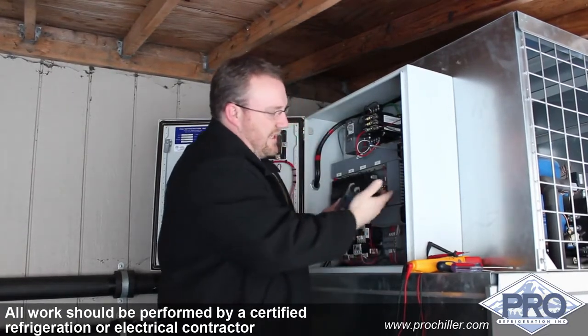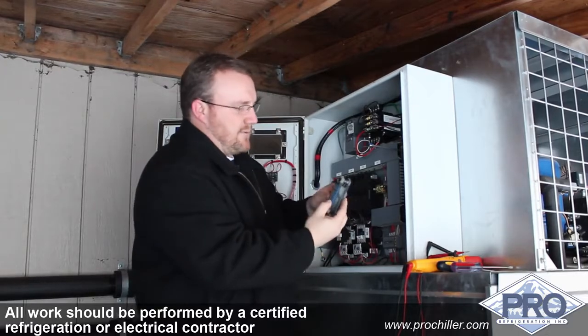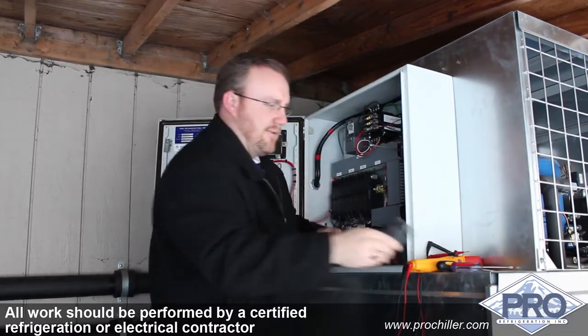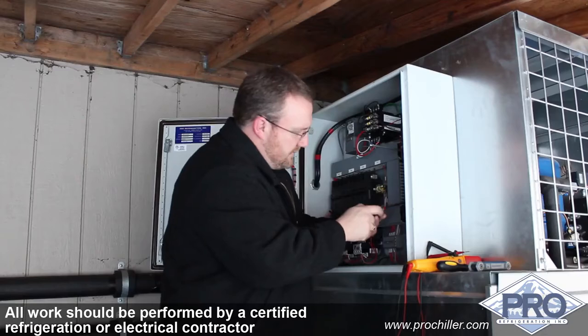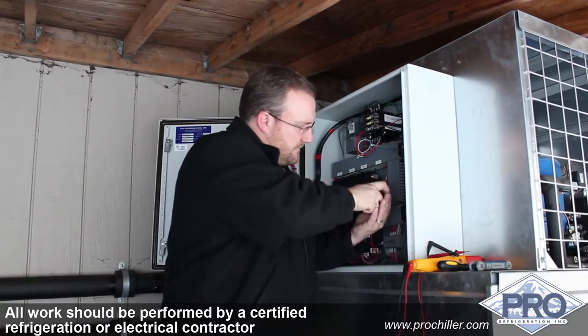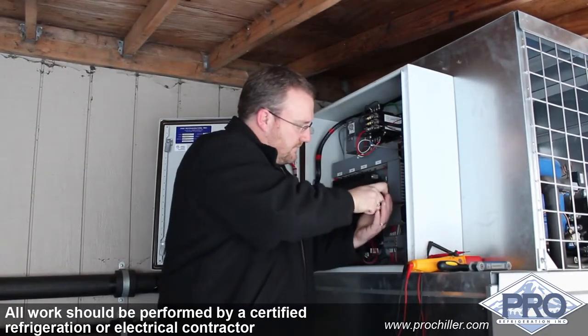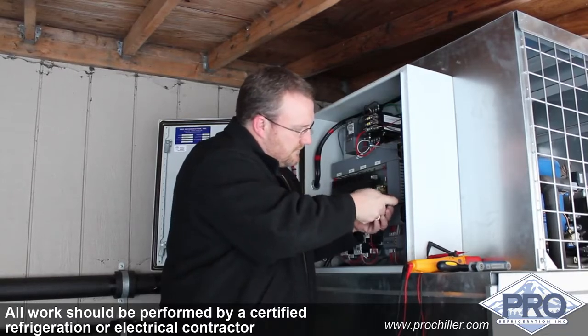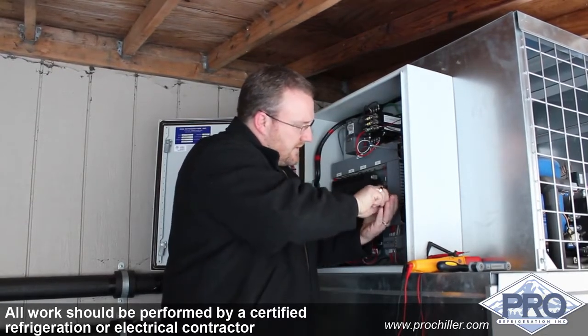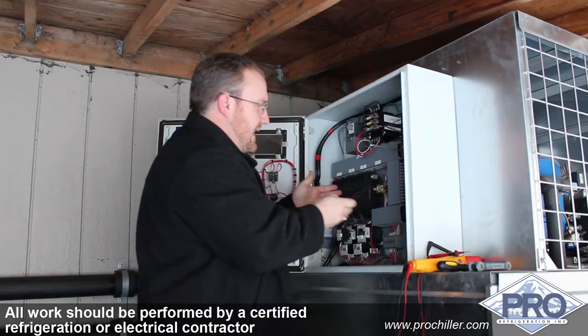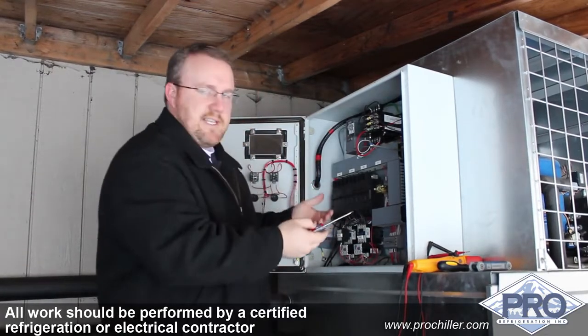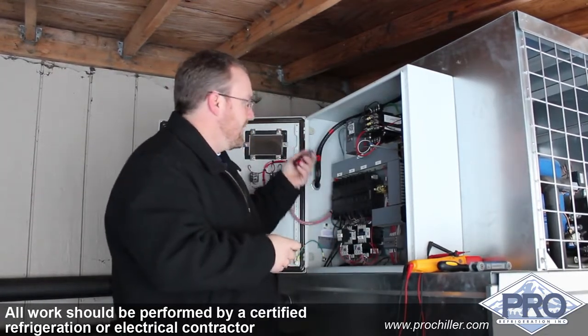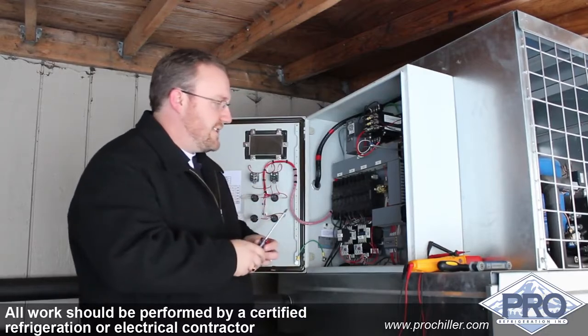That was tight. On the electrical distribution block, that's where you're going to require the use of your Allen wrench set. You just work your way through the entire electrical control panel doing the same thing, checking all of the electrical connections to confirm that everything's tight.